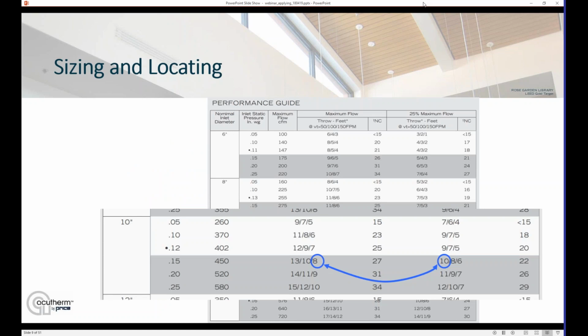What does all that mean? Well, something I think unique to Acutherm is we do have performance charts that show not only the performance of the diffuser at the 100% open position or design condition, but also at the 25% open or the turn down condition. So you do have that performance data to use when selecting your diffusers.